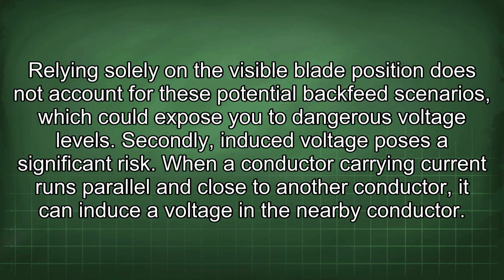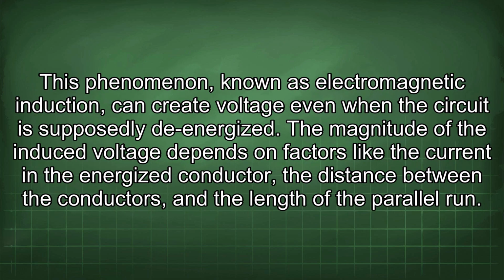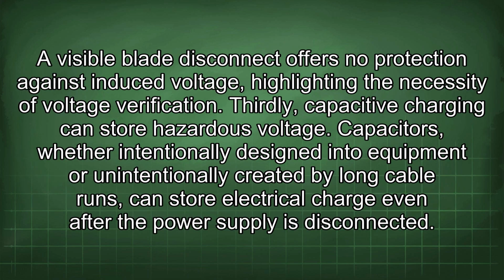When a conductor carrying current runs parallel and close to another conductor, it can induce a voltage in the nearby conductor. This phenomenon, known as electromagnetic induction, can create voltage even when the circuit is supposedly de-energized. The magnitude of the induced voltage depends on factors like the current in the energized conductor, the distance between the conductors, and the length of the parallel run. A visible blade disconnect offers no protection against induced voltage, highlighting the necessity of voltage verification.